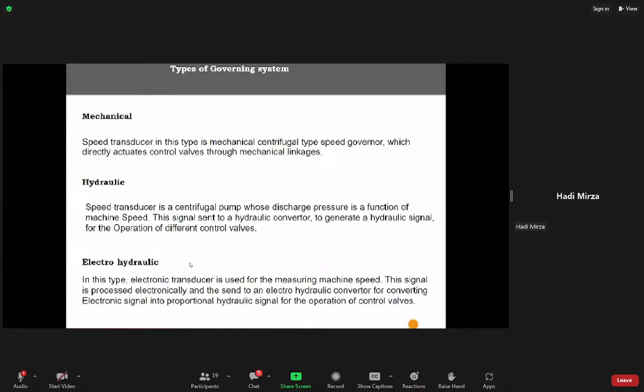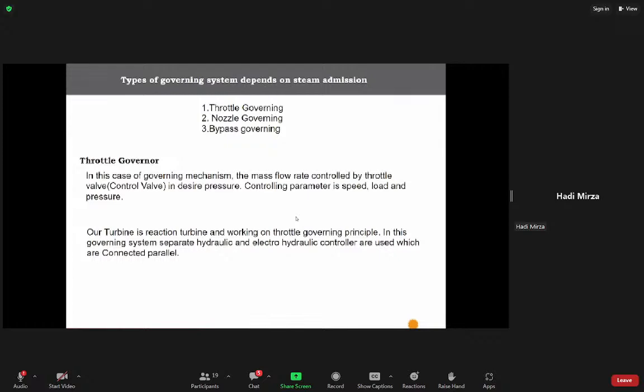Electro-hydraulic converter. In this, there are two sensors. One is the speed sensor, and the electronic speed signal goes to the electro-hydraulic converter, which converts it into an electronic signal and a proportionate hydraulic signal for the operation of the valve. This basically takes the signal from the speed sensor transducers and converts it into hydraulic pressure, and this in turn governs the control oil and control valves. Speed and load, everything will be controlled like this.